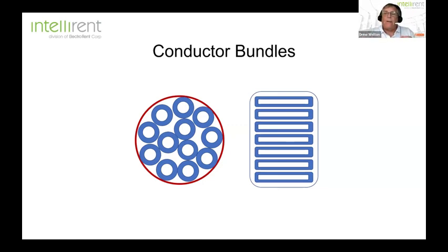Now, the way we build the windings of the transformer, it's not a solid conductor wrapped around the core. It's a series of conductor bundles with insulation in between each one of those little conductor strands. The one on the right is probably more like what we see here in North America, where you have these flat conductors and there's insulation in each one of those layers.